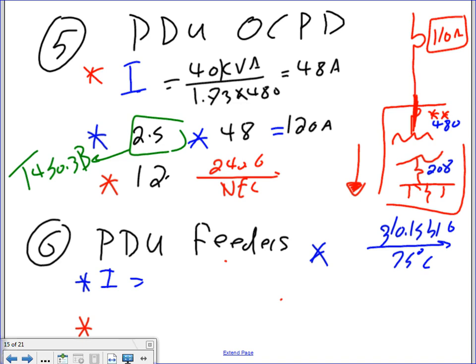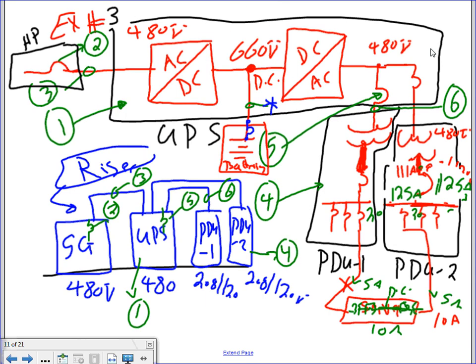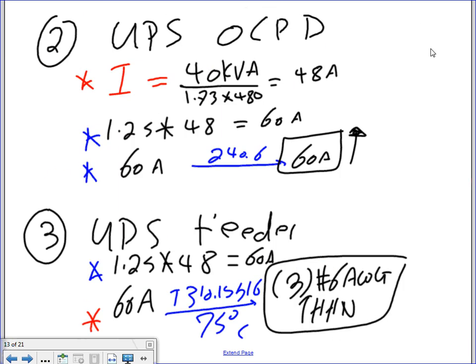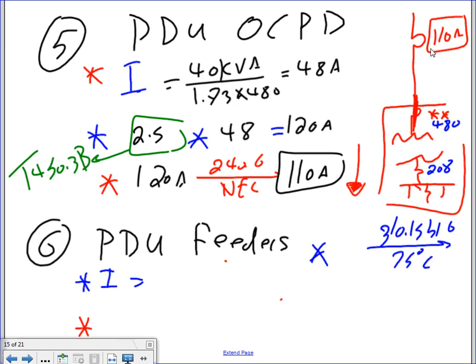Then you take the 120 amp, you drop it down to 110 amp. So I'm going to go right here, which in reality is going to be right here. Can you guys see that? Right here in that section of the UPS. The UPS will have a distribution section right here. In that distribution section, typically you have to tell the manufacturer, and they put a circuit breaker for you, 110. Now, if the manufacturer said, guys, no, we're going to make it 100, because they know their system, they can size them. We follow what they tell us. If they don't tell us, we use what we believe we need. Okay, so we got 110. So that's that one right here, 110.